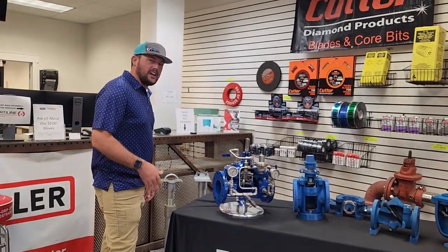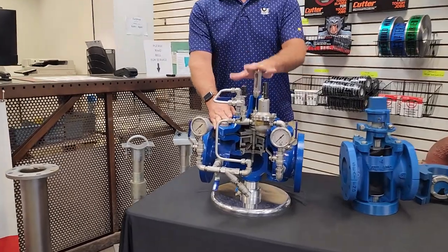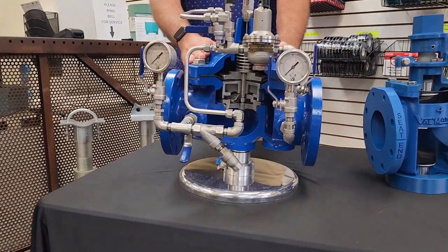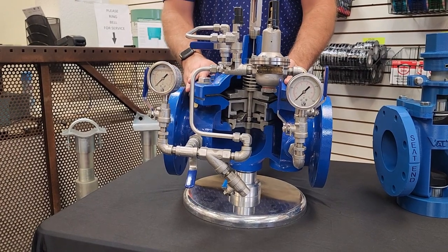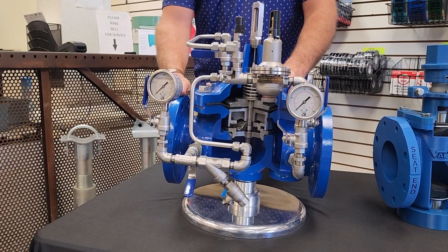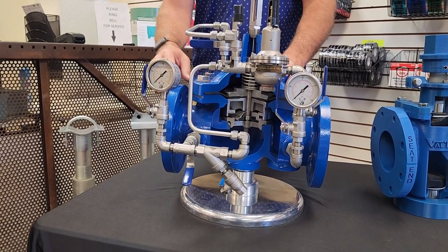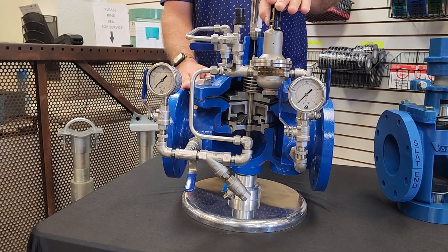So, starting out, real simple right here is Cla-Val's main valve. As it's set up right now, this is a pressure reducing valve. This one you'll see in most applications out in the field. The way this valve works is you'll have the inlet side here. As we know, this would be the inlet side.